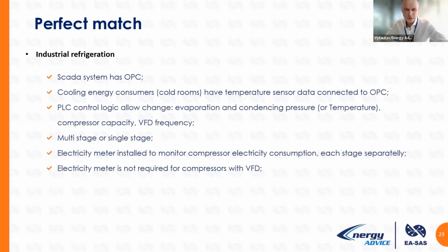Also, one trick that is not written in the slides: we found that optimization of the compressor capacity control strategy in some cases allows clients not to buy a variable frequency drive. Multi-stage or single-stage, electricity meters should be installed on the compressors to meter the electricity of the compressors. And if you have a variable frequency drive, it has a frequency metering value and an electricity active power value, so we don't need to install an electricity meter.